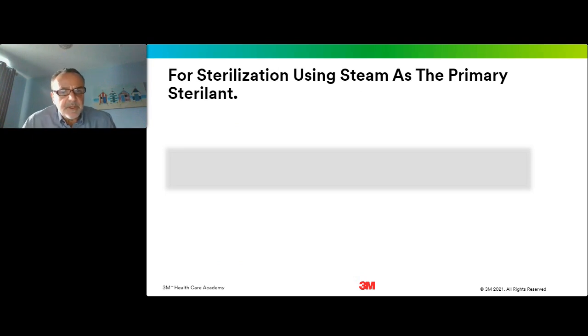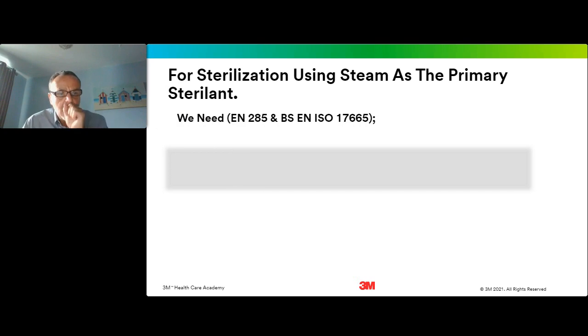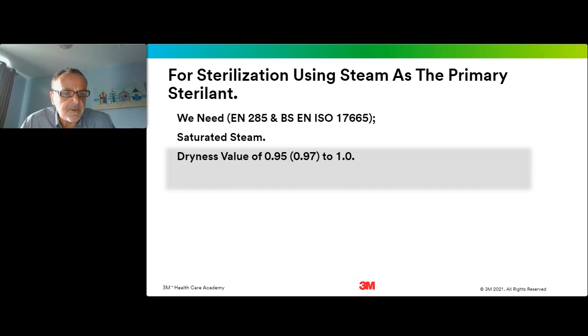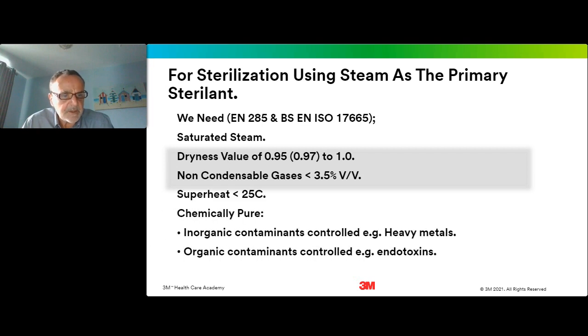So for sterilization using steam as the primary sterilant, there are certain requirements. We should use saturated steam. It should have a dryness value of between 0.95 and 1, and I note in your own US standard you have a minimum of 0.97 there. The non-condensable gases should be 3.5% or less. Superheat should be less than 25 degrees C, and the steam should be chemically pure.